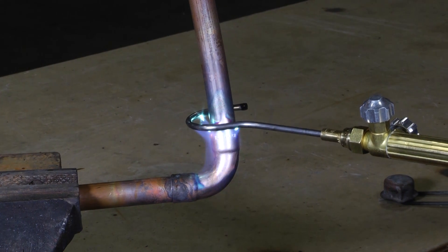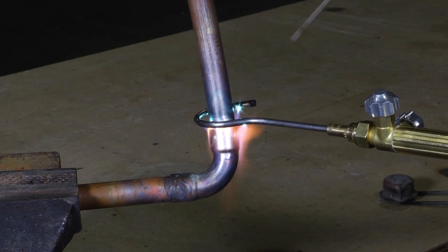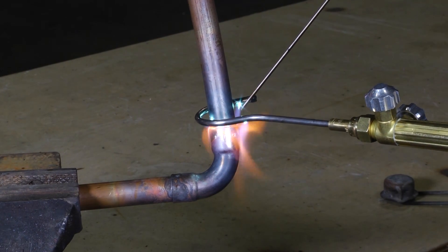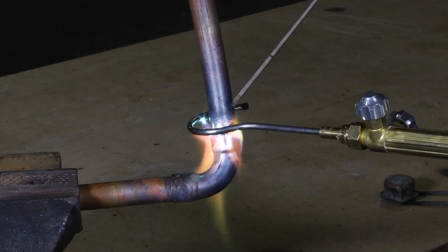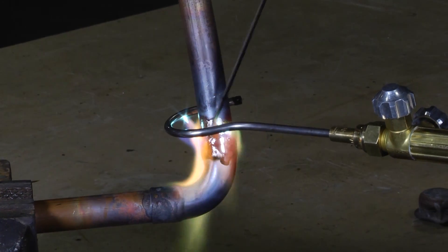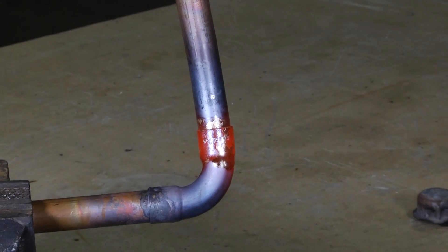Once you get your hook ready and heat your copper, you can just hold it in one place. The copper will start to turn red. Once it's ready, all you do is just touch it and that Silphos will wick all the way around and go all the way around our joint — it'll just suck our Silphos right in there and that's done.